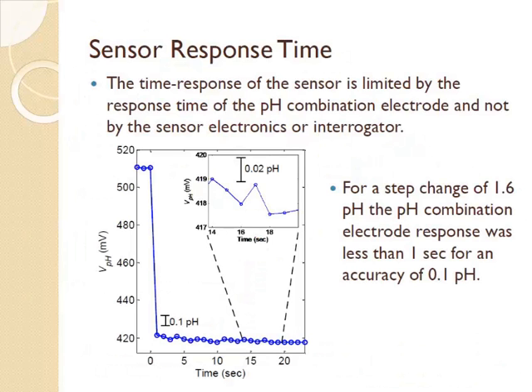Another important thing for the sensor was the response time, because we wanted to monitor the milk quality in real time. We found that the response time is not limited by the electronics of the circuit or the interrogator coil, but by the response time of the combination electrode. So we put the combination electrode in a standard 4 buffer solution, and we added some base and did a step change of 1.6 pH and monitored the voltage across it. We found that to have a 0.1 pH accuracy in our measurement, we can reach that value within 1 second. So we can get a response time of 1 second if we want 0.1 pH accuracy in our measurement.